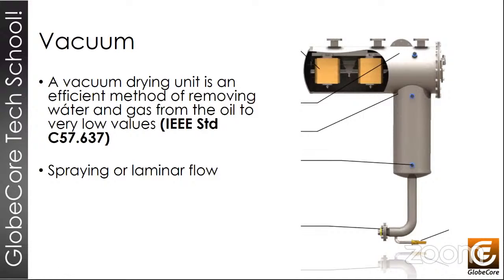So based on IEEE standard C57.637, we have our laminar-shaped vacuum tanks in order to have more oil exposure inside the vacuum chambers and to improve the procedure and its results. So here we have elements. You will see the yellow ones. Those are called activator filters. The oil flows across them as it passes through the chamber. And in this vacuum chamber, we have 3 inlets, not 1. So the oil passes over aluminum plates, which greatly increase the surface area of the chamber, and they make the vacuum process a lot more efficient. Next, please.